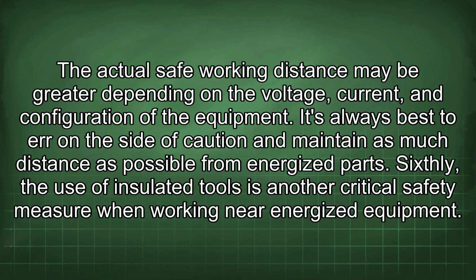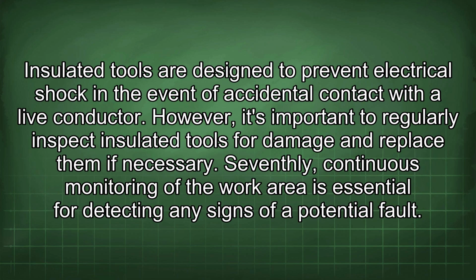Sixthly, the use of insulated tools is another critical safety measure when working near energized equipment. Insulated tools are designed to prevent electrical shock in the event of accidental contact with a live conductor. However, it's important to regularly inspect insulated tools for damage and replace them if necessary.